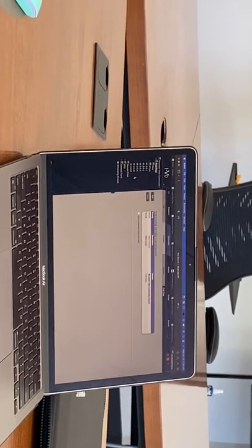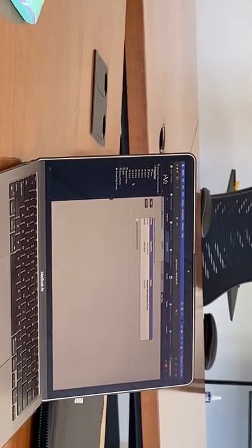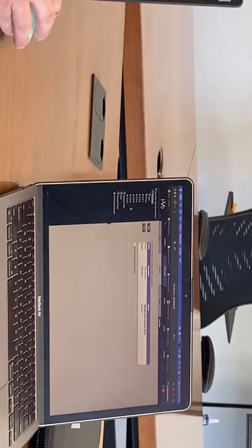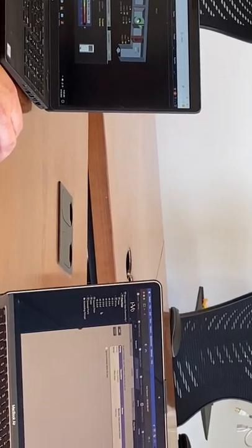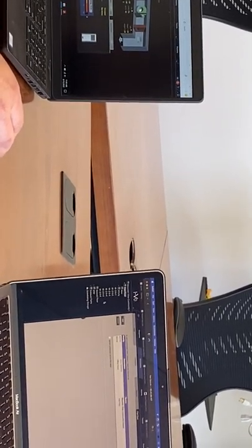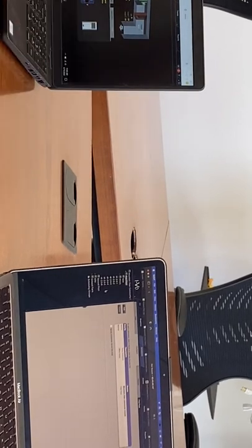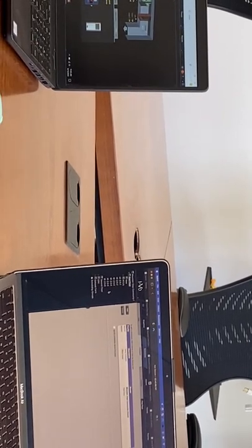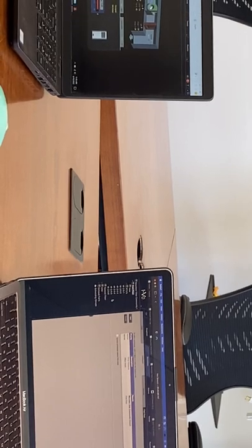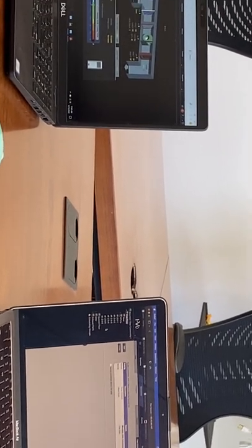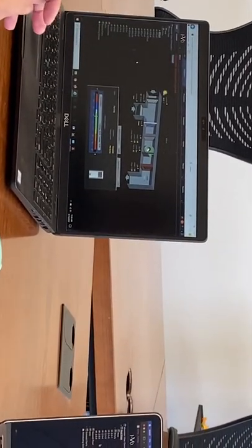When setting schedules, it always works its way up in priority. If I set a schedule on First Floor it applies to everything below it. If I also have a lower-level schedule in Normal mode, they'll fight each other. So it would be fair to say he should only program Normal schedules in each sub-area, and if he's doing First Floor level it should be Holiday or Override.